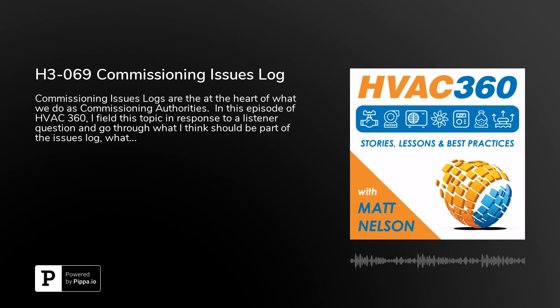That is really important. Another example of this, the freezestat one. I can go either way, and you can see how that number is highly variable. But say, for instance, your boiler flues. If your boiler flues were right next to your outside air intake for your air handling unit, well, what would it cost to actually move that? And you can get some pretty hard numbers to actually moving that after the fact, because obviously that's a code issue, and you want to be able to remedy that.